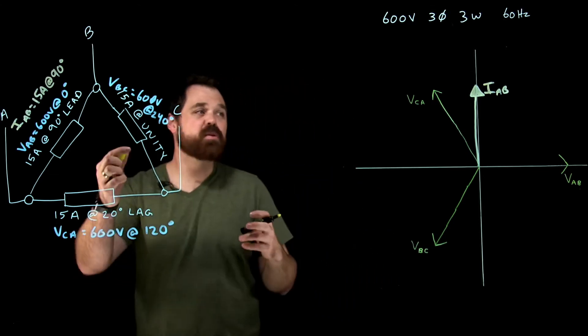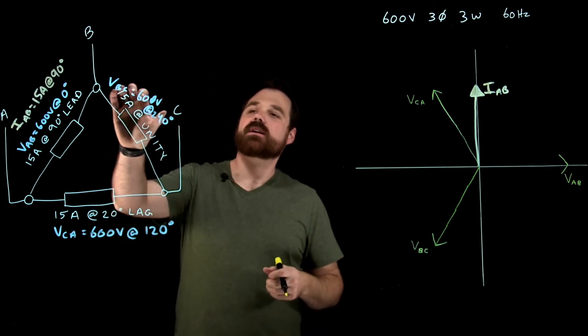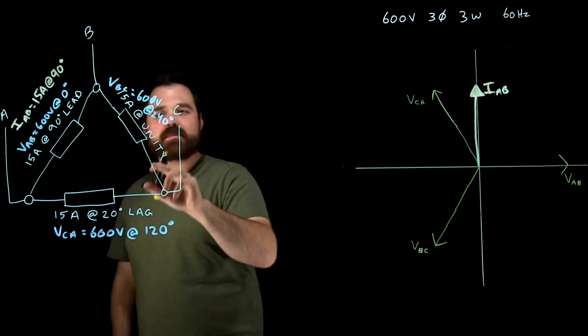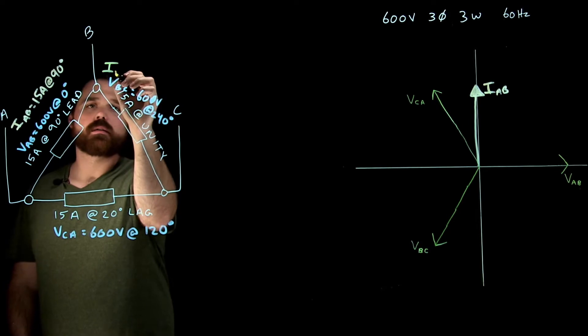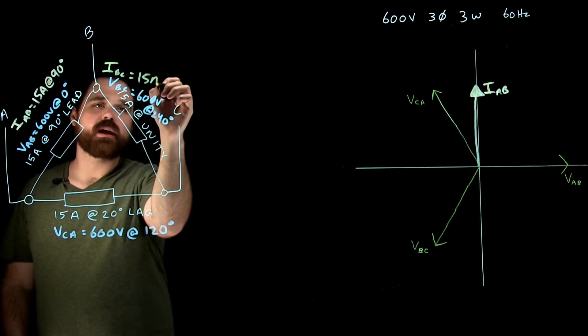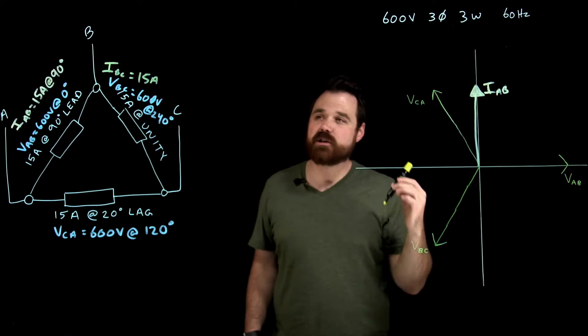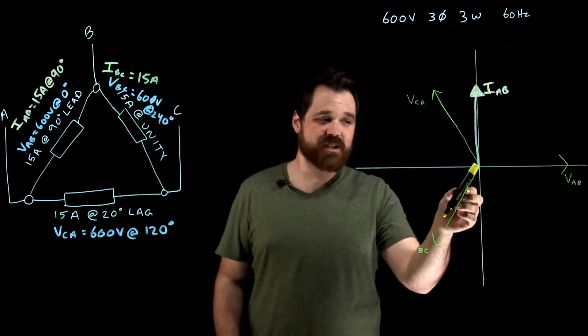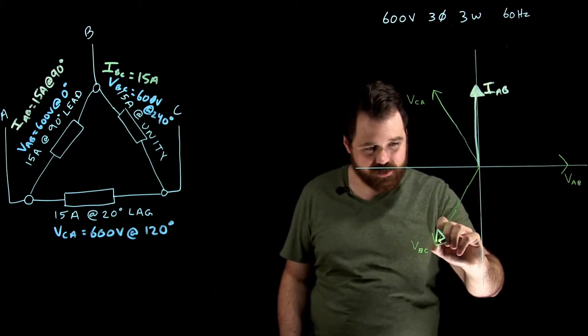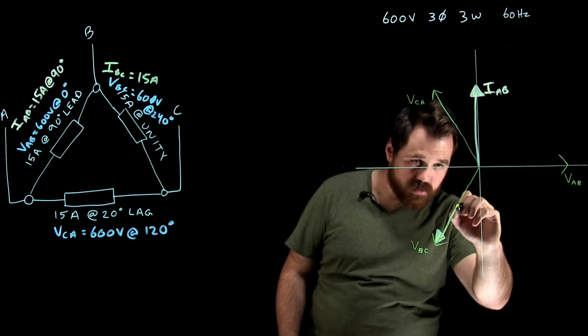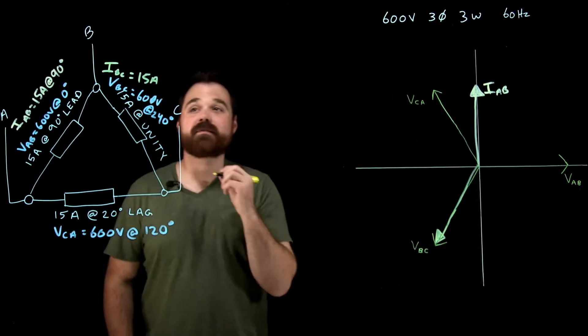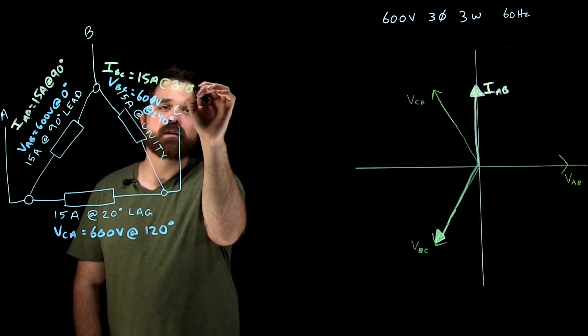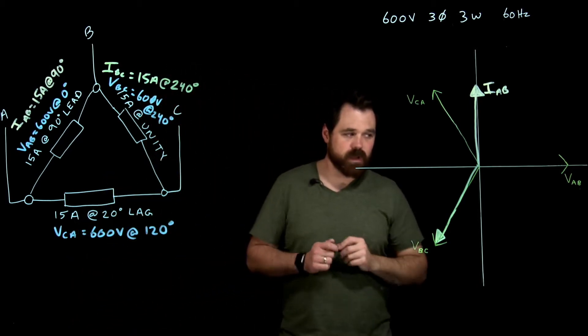Now let's talk about the B phase current. So the B phase, I've got 600 volts at 240 down here. Now I've got 15 amps at unity. So we know I B to C equals 15 amps. Now it's at unity, which means that the current and the voltage are in phase with each other, which means that my current is actually going to be right here directly on top of my voltage, which puts it at the same 240 degrees.